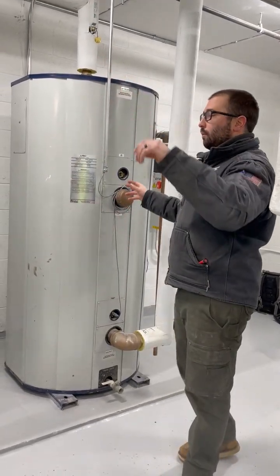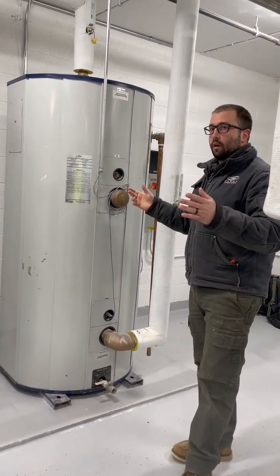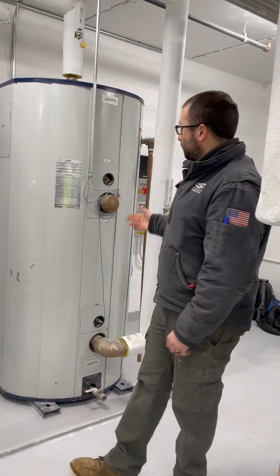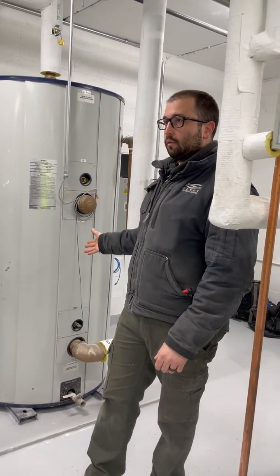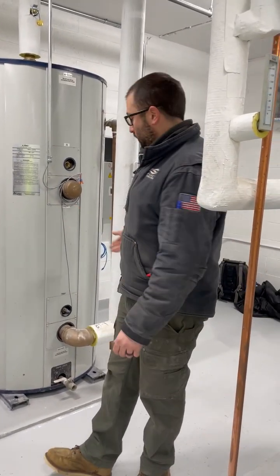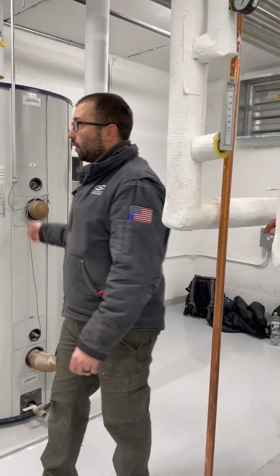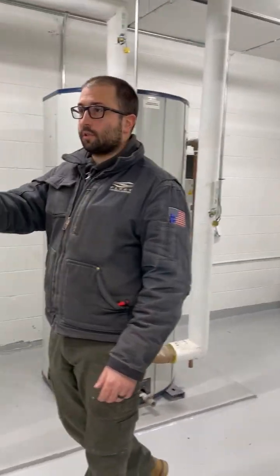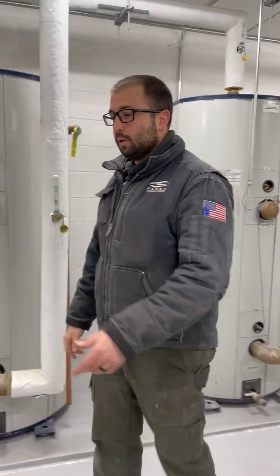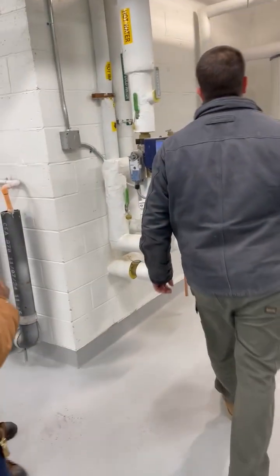So in series, does that make sense? Putting hot water into there, pulling from here. Now that's on a recharge. Now when people are using the showers, domestic cold water goes back the normal way, like an electric hot water tank. Cold water comes into here, it pushes through all the tanks and pushes hot water to the mixing valve over there.